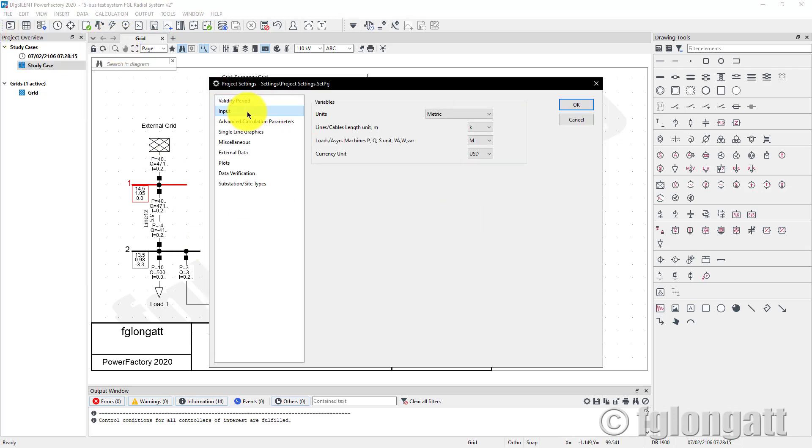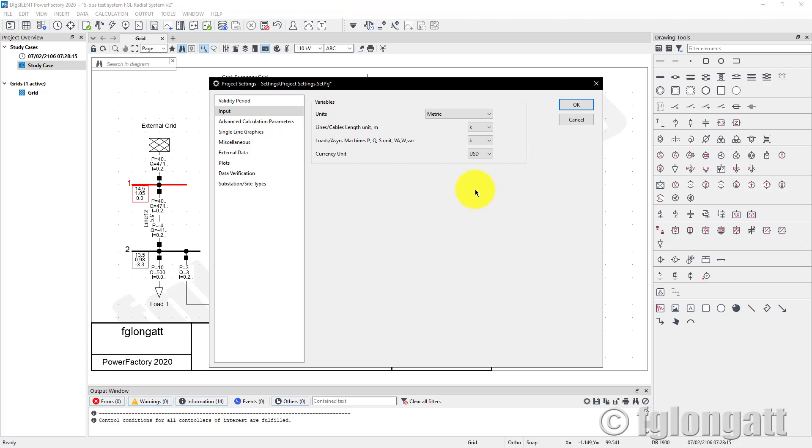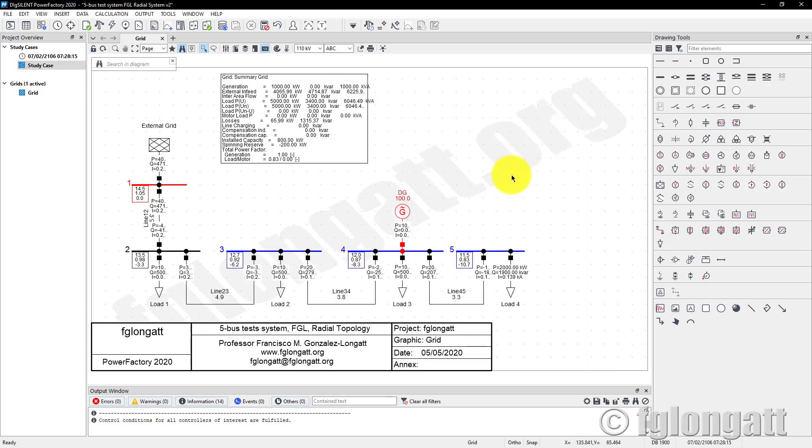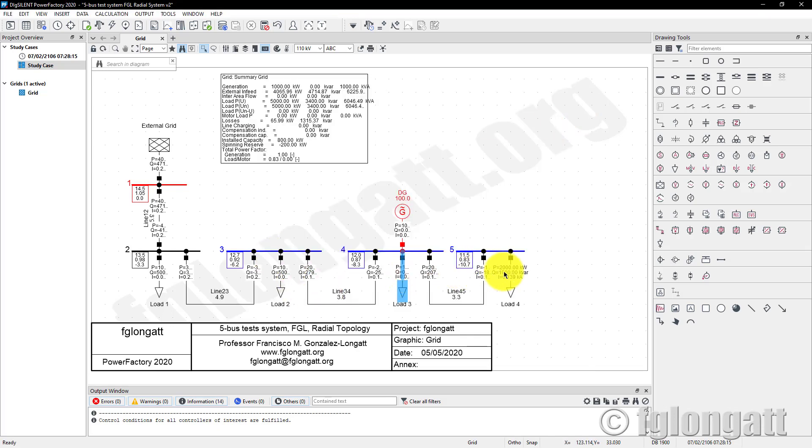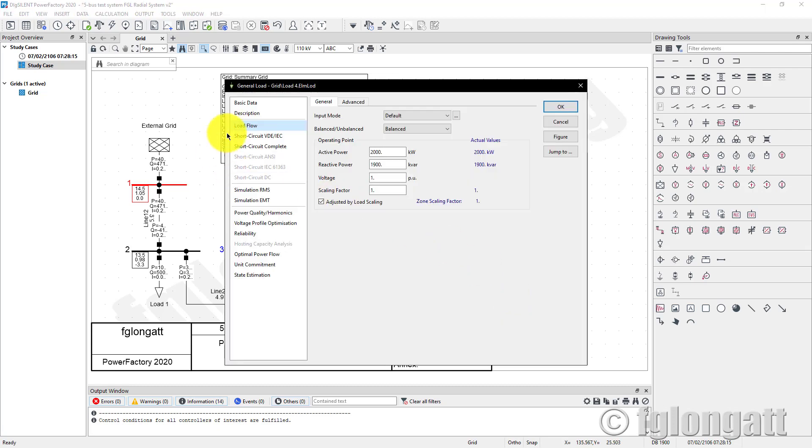What I am telling you is that using the project settings you are able to change the configuration of the input data. If you are working in an industrial system or distribution system, you probably want to use the inputs as kilowatts or kVAR. As you can see, double click and now PowerFactory is showing the input data using kilowatts. Now you are able to see the results on the output boxes using kilowatts, and also input the data using kilowatts. That solves a lot of issues for people at distribution systems and in industrial companies.